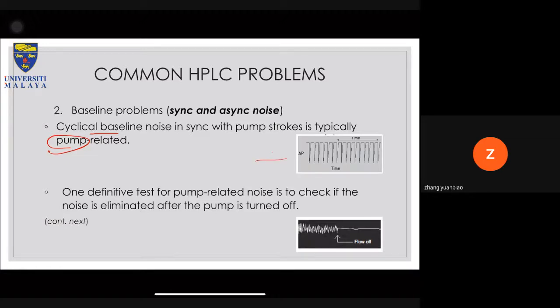and therefore you can get a baseline problem as shown in this picture here. One definitive test for pump related noise is to check the noise is eliminated after the pump is turned off. So either the pump is off straight away from the start and you cannot hear the noise, or it might be that initially there's a noise, and then when you stop the pump, then either the issue goes away or you eliminated the issue that you observed from the detector. So you know the issue now is related to the pump.